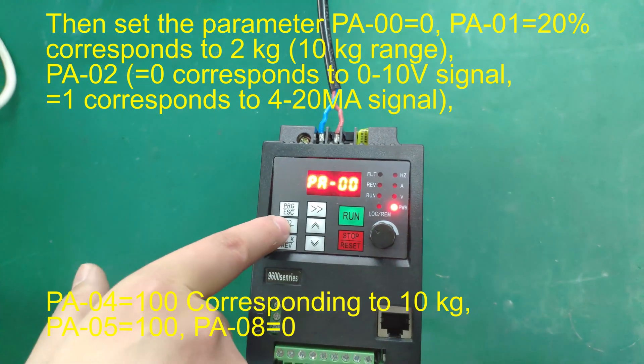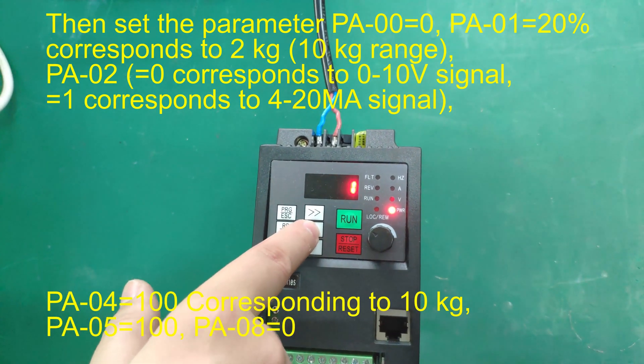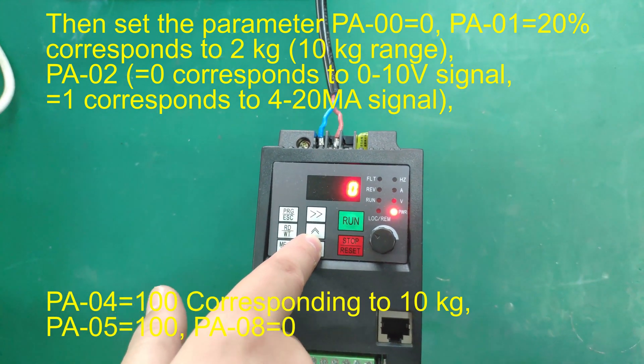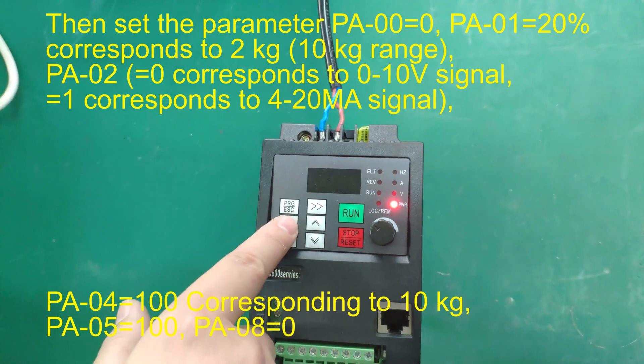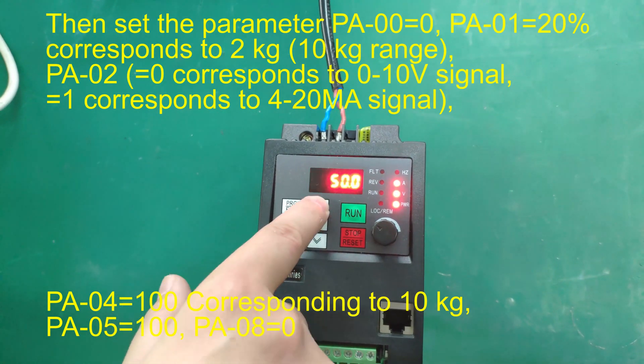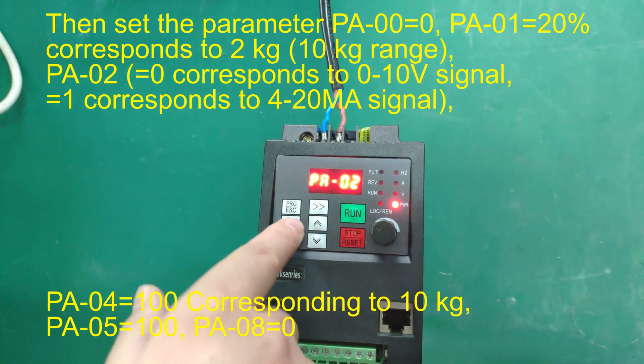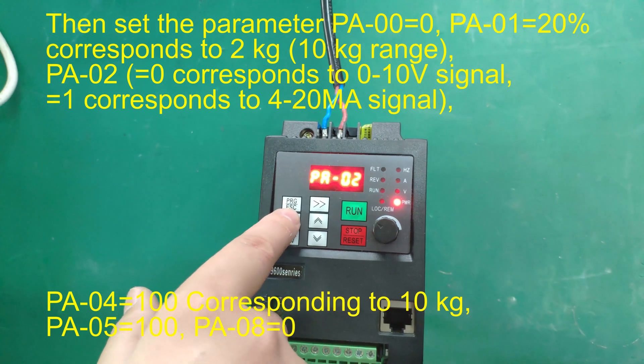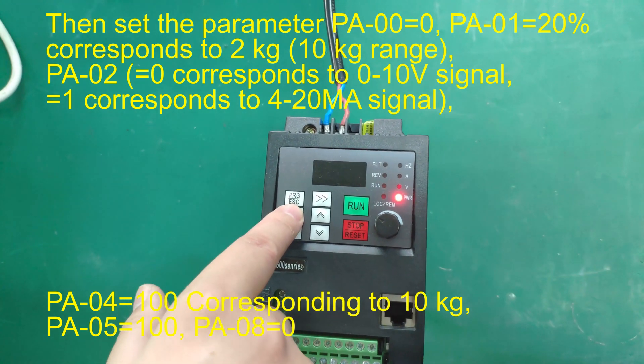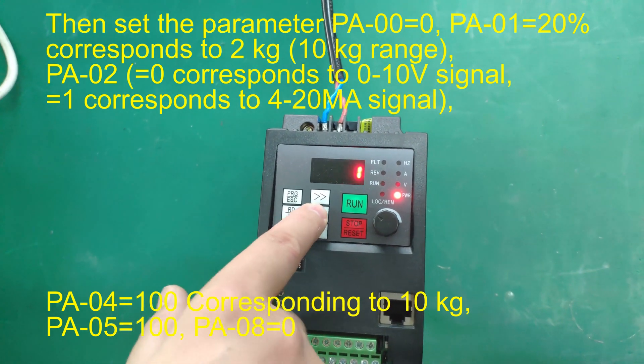Then set the parameter PA0=0, PA01=20% corresponds to 2kg (10kg range), PA02=0 corresponds to 0-10V signal, =1 corresponds to 4-20MA signal.